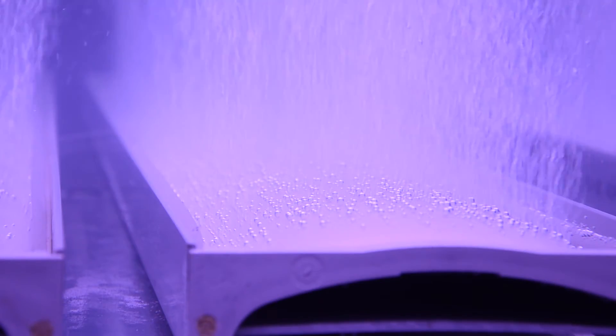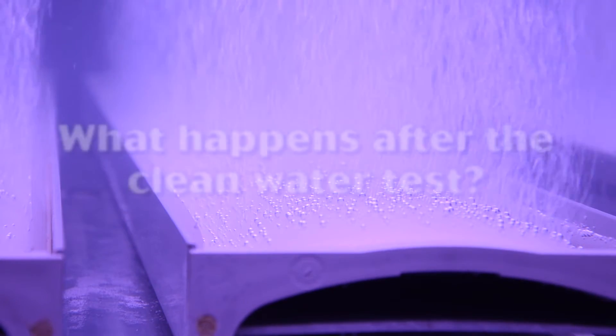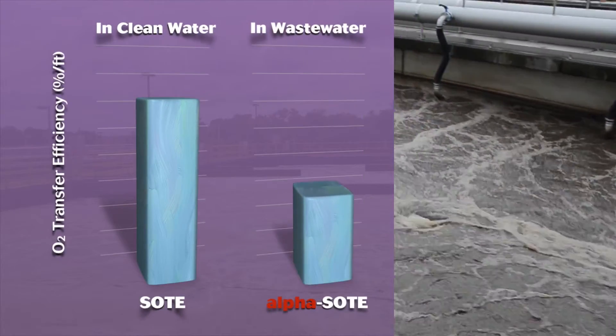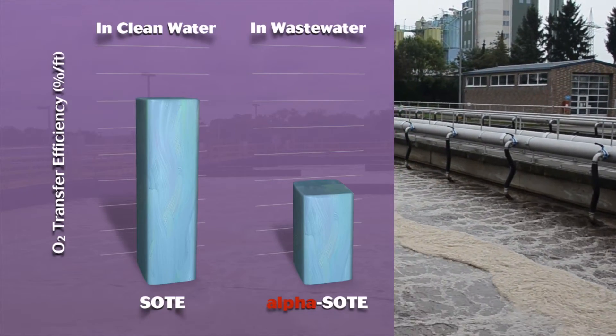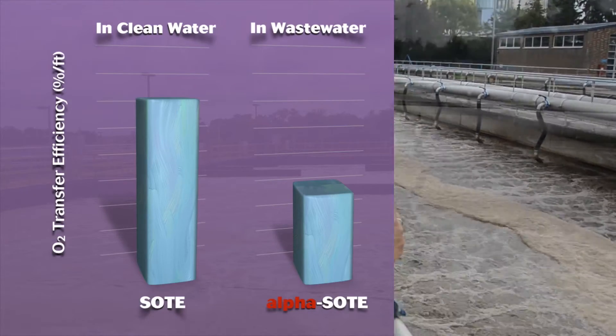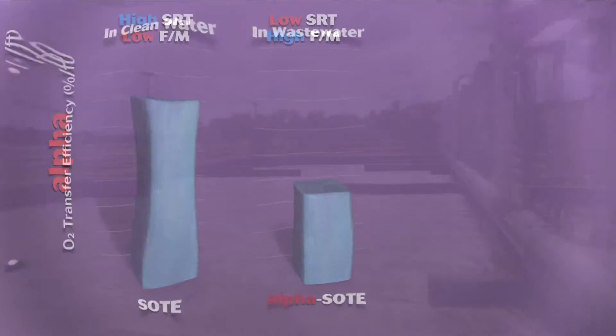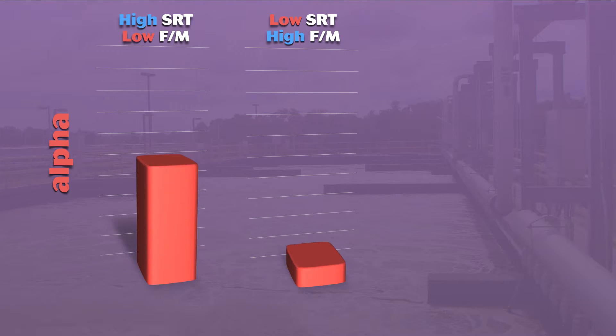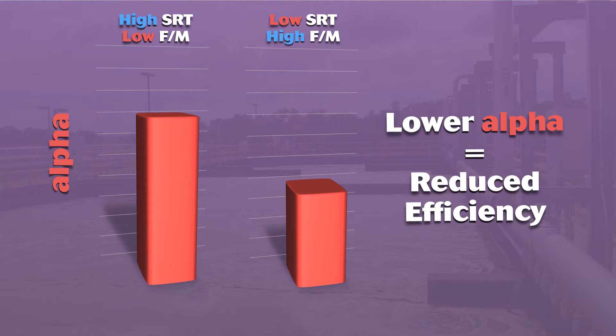But clean water transfer is only part of the story. The more important question you should be asking about your diffusers is: what happens after the clean water test? In real-world applications, the environment for these diffusers is not so friendly. The presence of surfactants such as detergents and biologically produced materials will inhibit transfer across the bubble surface into the wastewater. Plant design and operation can also impact the alpha factor — low SRT or high F to M generally reduce alpha and therefore lower efficiency.